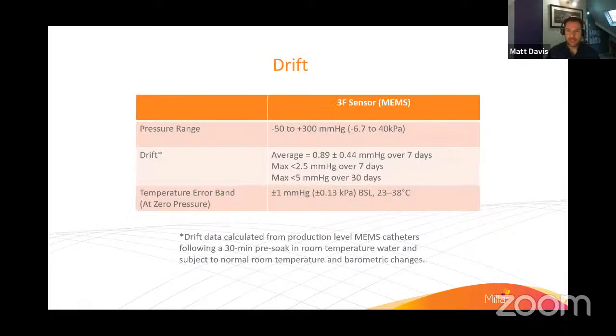Coming on to drift: one of the main areas of discussion with potential clients is around drift and how to minimize it. Drift occurs when electronics heat up and parts are subjected to liquids of varying temperatures. This is not specific to Millar technology, but to all pressure transducers. They all have some form of drift through the warming up process, and to minimize this, we advise a pre-soaking period to stabilize the catheter and signal.